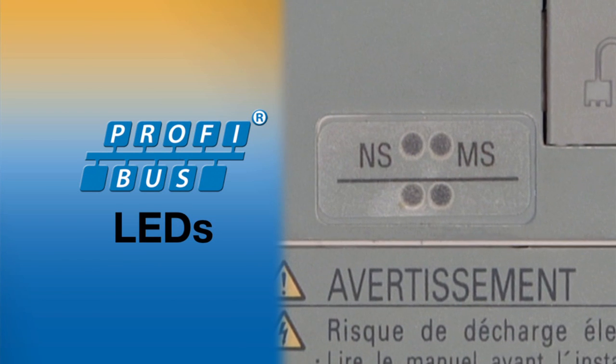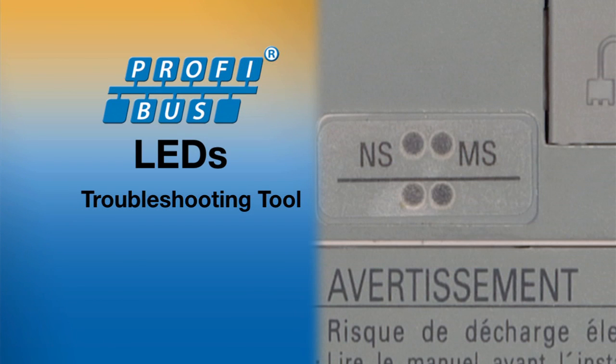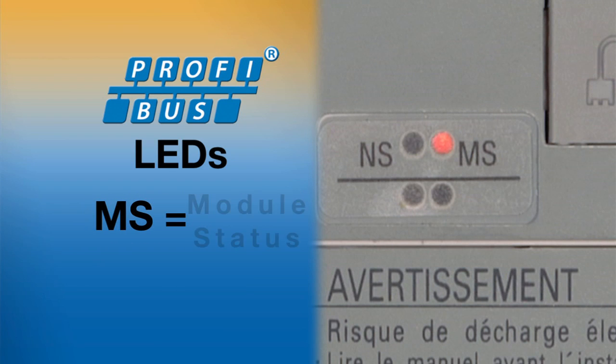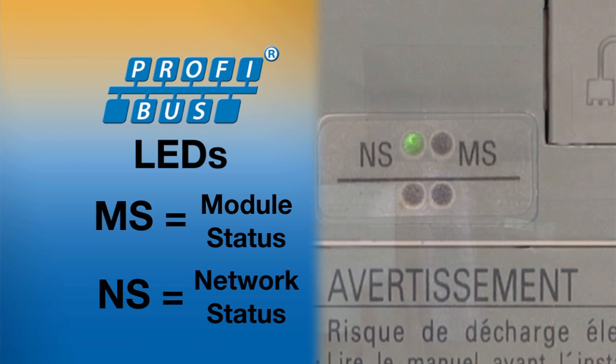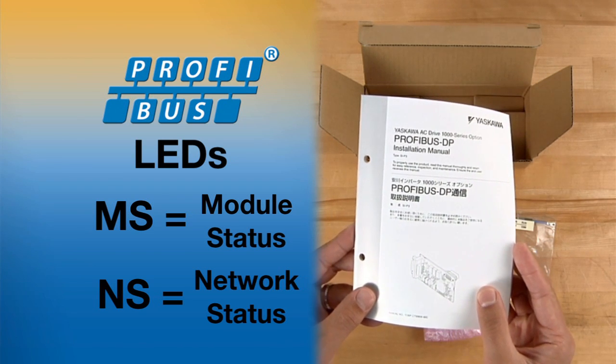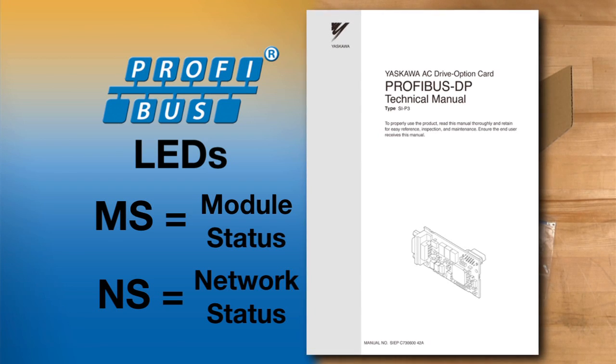The PROFIBUS LEDs MS and NS are both a troubleshooting tool and a point of access to determine system functioning. Check the status of these LEDs which are visible through the cover of the drive. The MS light indicates module status. The NS light is network status. Complete information on interpreting the meaning of the LEDs is in the technical manual that came with your SI-P3 option card.